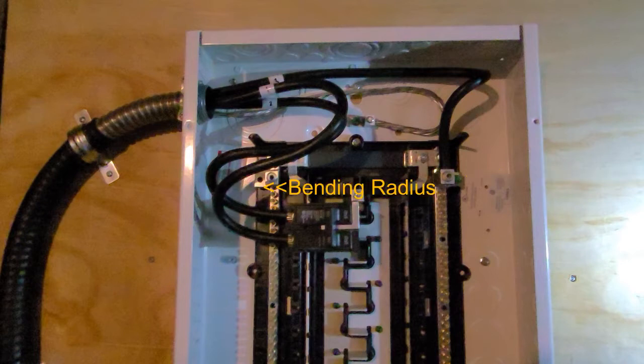Secondly is the cable bending radius. For this low voltage cable, you can bend it no tighter than 6 times the diameter of the cable. If you bend the cable too much, you actually put stress on the cable, especially if you're dealing with aluminum conductors. And after that, we also need to talk about the torque of the 2 breaker screws here. Again, this breaker is rated for aluminum and copper, but you do need to apply a certain torque on the screw, so make sure you have good connections here.